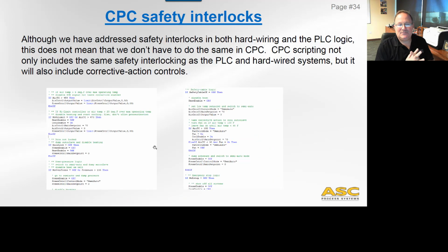And now we're moving on to the CPC interlocks. And we're almost done with this training. I'm going to run you through some of the scripting here. So although we have addressed the safety interlocks in both hardwiring and PLC logic, this does not mean that we don't have to do the same in CPC. Okay, CPC scripting not only includes the same interlocking as the PLC, but it will also include the corrective action control that we talked about in the PLC coding, or not being in the PLC coding. So basically, CPC is going to not only interlock, meaning turn things off, but it's also going to turn things on to correct safety conditions or over pressure, over temperature conditions.